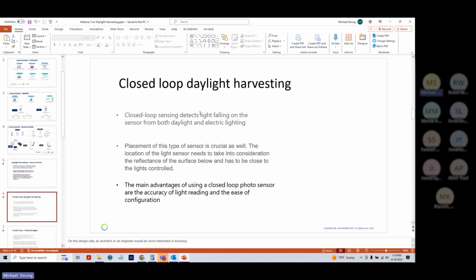So the next slide, we're going to talk about closed loop daylight harvesting. Closed loop detects light falling on the sensor from both daylight, that's the sun coming in from the windows, and electric lighting, so the lighting produced by the light fixtures. And that's important to note because that's a combination of lighting. There are several factors that go into the way that we detect lighting. Typically, we're picking up a reflection of the light and not directly the sun coming in. So it hits the floor, bounces, and we're capturing the artificial light above the floor, along with the daylight. That's what a closed loop system does. And then it sends out the instructions from there through our chipset and into controllers, so the controllers then react accordingly.